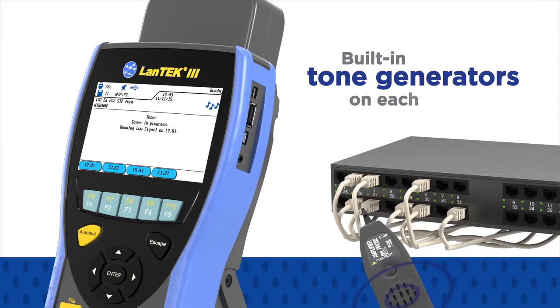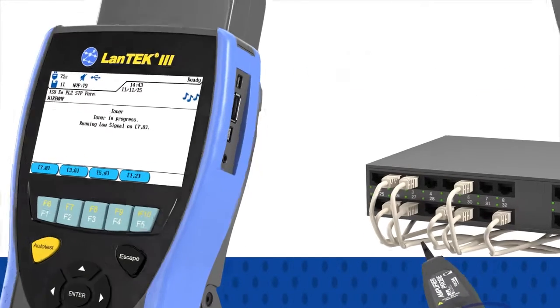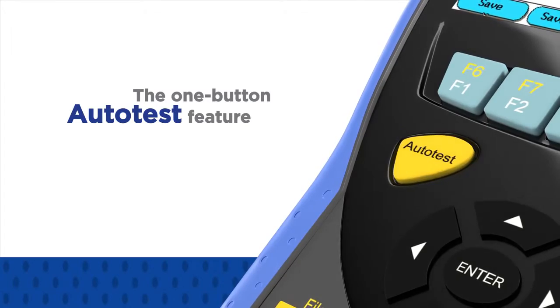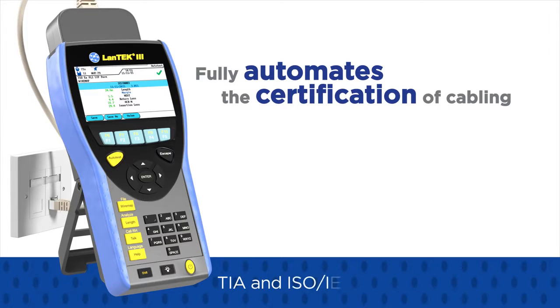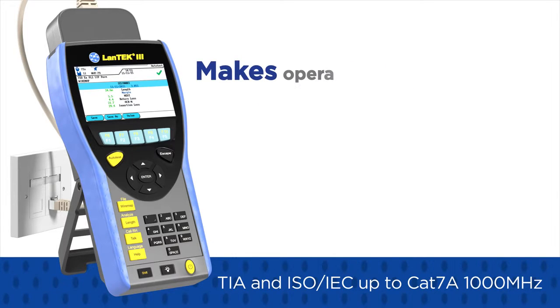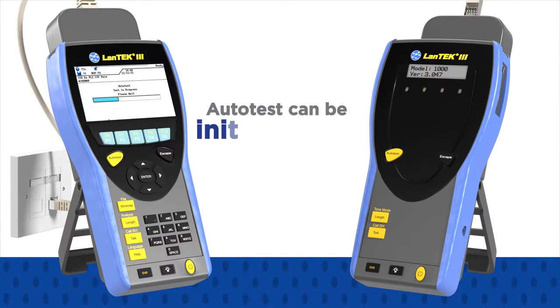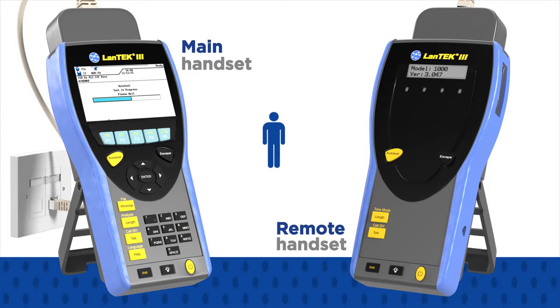Additionally, built-in tone generators on each handset allow identification and tracing of cables with a standard amplifier probe. The one-button auto-test feature of the LanTEK III fully automates the certification of cabling to TIA and ISO IEC performance standards up to CAT7A 1000MHz, making operation and result capture extremely simple. Auto-test can be initiated from either handset, which saves time when one person is testing.